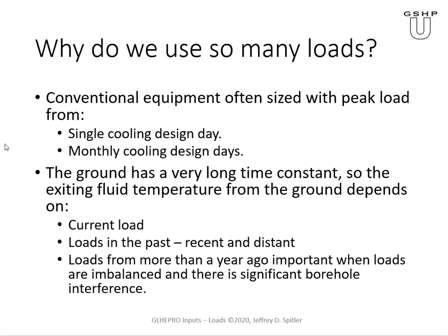And furthermore, loads from even more than a year ago are important, particularly when the loads are imbalanced and when there is significant borehole interference. It's not so important if the loads are perfectly balanced over the year, then we don't expect a significant effect of loads from more than a year ago. But if they have moderate to large imbalance, then the temperature will tend to build up over time or draw down over time, depending on whether we have an excess of heat extraction or an excess of heat rejection. Also, this is more important in cases where there's significant borehole interference.